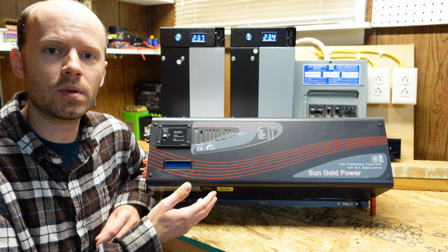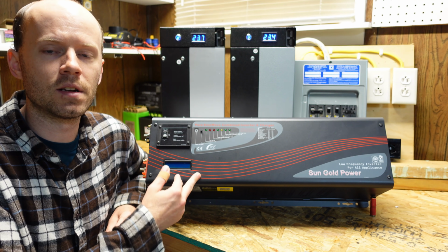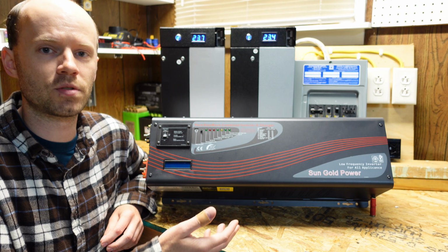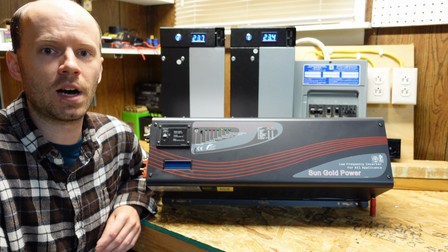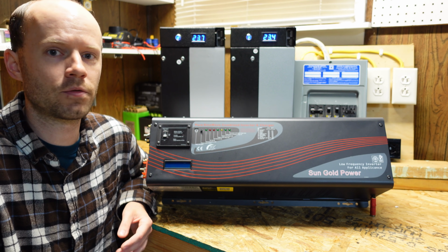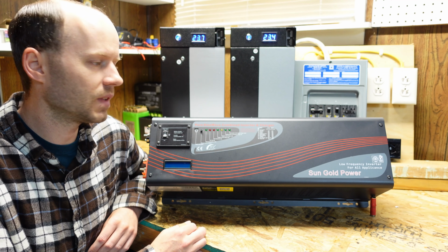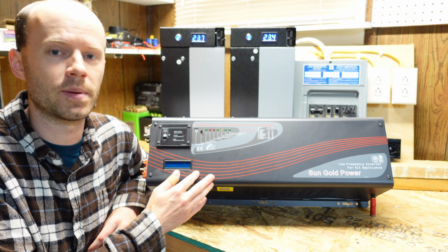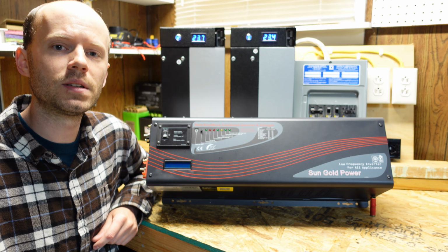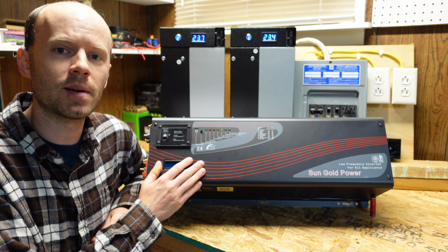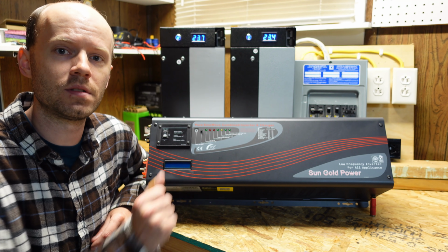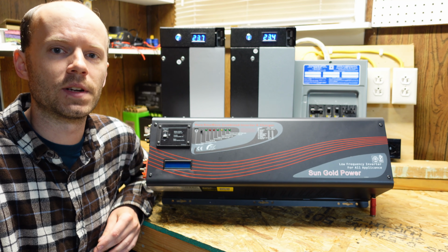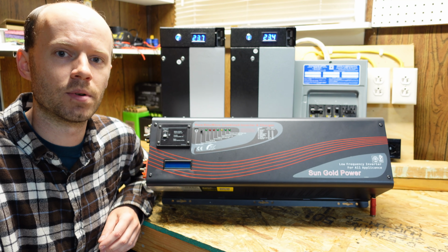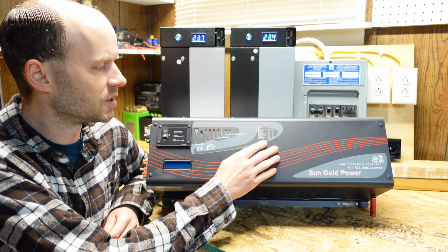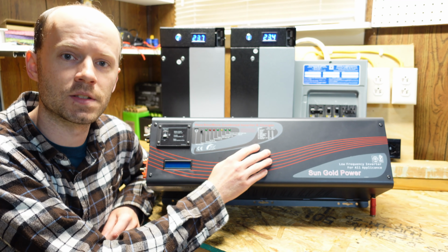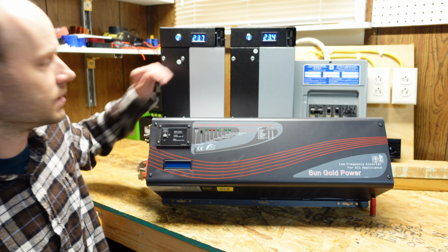And where that becomes important is like if you're using this for your home or backup, let's say your air conditioner is on or your clothes dryer is on, and not have to worry about shutting something off if you have to flip on a microwave temporarily, your fridge kicks in or something like that. And you won't find that kind of overload or starting capacity on a high frequency inverter. Additionally, this has a 120 amp charge controller built in if you choose to use it. I know the inverters and whatnot that I'm running, I typically don't connect the grid input to it. However, this inverter is specifically designed with lithium iron phosphate in mind, so it pairs perfectly with these lithium iron phosphate batteries.